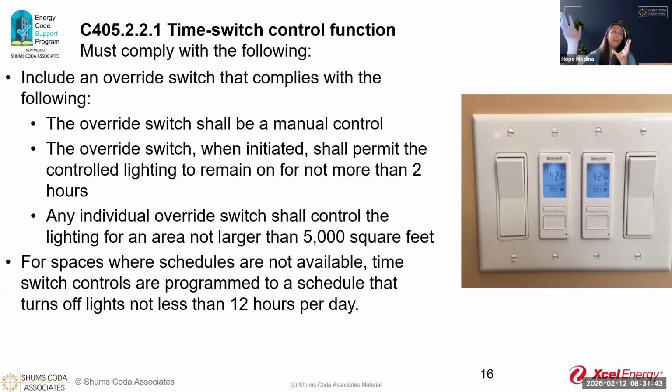Now that override switch can do a space that's up to 5,000 square feet. So if it's larger than 5,000 square feet, you're going to have multiple override switches for that.